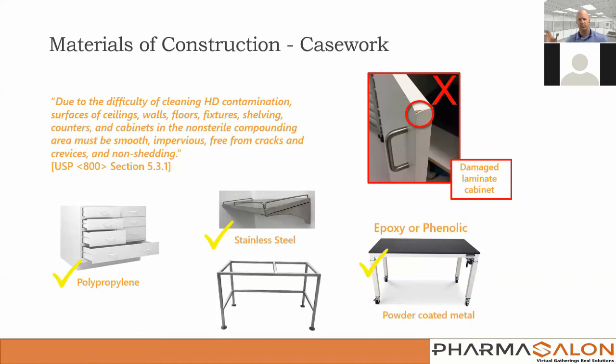So what's the solution to those materials? You can go back with an IPA. Now, if you're in your clean rooms, you want to use a sterile IPA. You want to pull up that surfactant. Now, remember I told you IPA can also do that, but it takes a lot more of that residue. So you can also go back with sterile water and then do a post-wipe periodically. You don't have to do it every single cleaning protocol, but periodically your goal is to remove any of that residue off of those cleaning materials so that they don't start to rust out. So there are solutions, there are workarounds. Yes, it's going to be much more labor intensive.